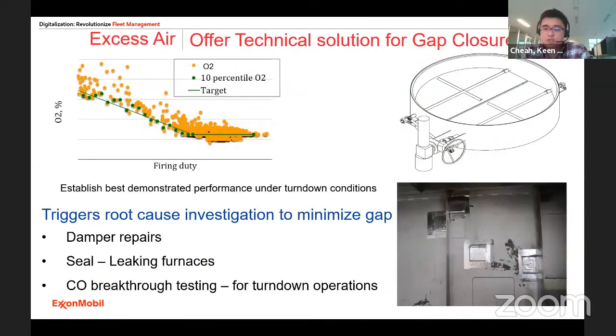This first example shows a case where excess air, or excess O2, has been high, and the tool was used to offer technical solutions for gap closure. Looking at the chart on the top right, the green line is the best demonstrated excess O2 as a function of firing duty. There's a threshold duty above which stack excess O2 is constant, and below which it increases, which is inherent to the nature of furnace performance.